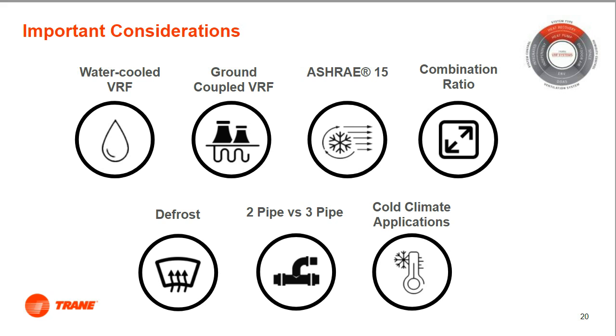Also, when designing a VRF system, it is important to determine whether the capacity of your system should exceed the 100% indoor to outdoor ratio. When a system has more indoor unit capacity connected to it than provided by the outdoor unit, we say that the system has a diversity ratio. Exceeding a system's diversity ratio means that if all zones call for heating or full cooling, then each zone's total capacity will be derated by the amount of diversity on the system. So, it is important that when designing a VRF system, your demand for capacity be distributed throughout the zones served by the VRF system.